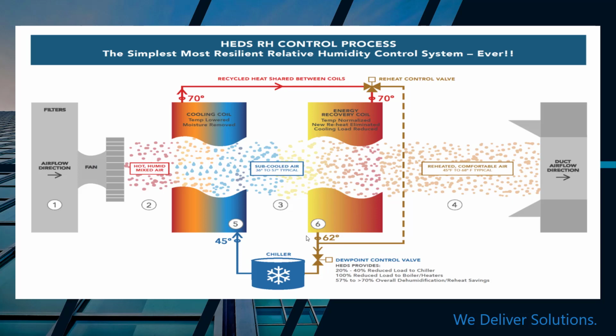and deliver lower temperature back to the chiller, which reduces the chiller load. It's an exciting piece of technology, been developed in California for many, many years and been vetted by the U.S. military for use in laboratories. For humidity control, we think it's the most energy efficient approach available. You really allow the air handler to do the control of the chiller plant when it's done correctly. So keep that in mind.